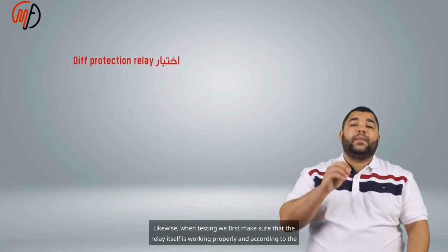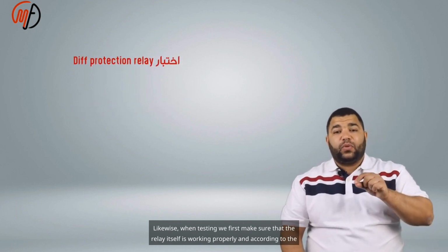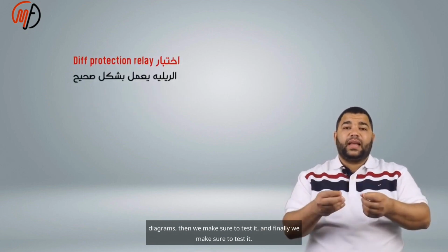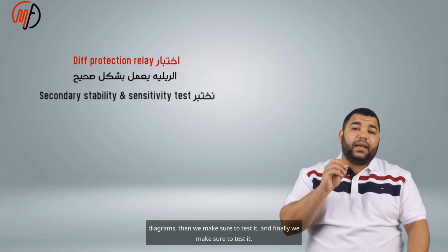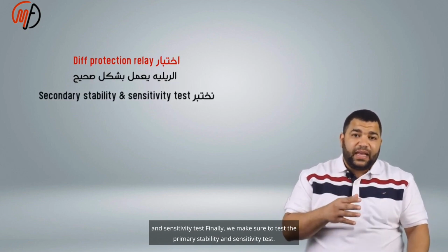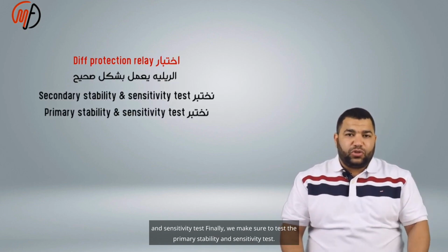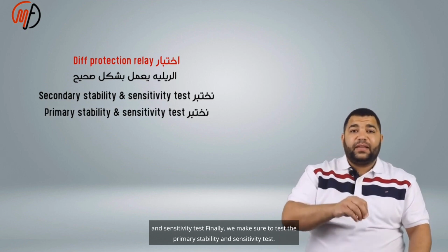Likewise, when testing the protection, first make sure that the relay itself is working properly and according to the diagrams, then we perform the secondary stability and sensitivity test. Finally, we make sure to test the primary stability and sensitivity test.